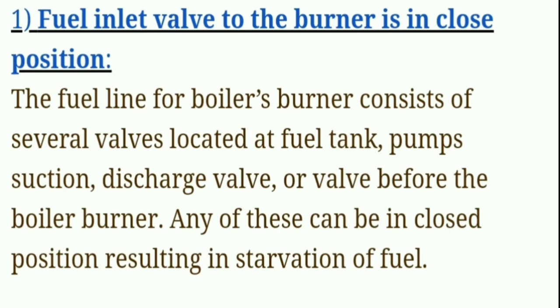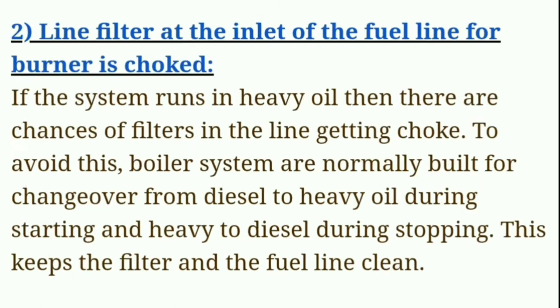First, the fuel line for the boiler's burner consists of several valves located at the fuel pump suction, discharge valve, or valve before the boiler burner. Any of these can be in a closed position, resulting in starvation of fuel.